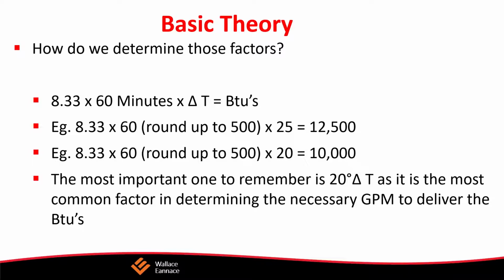Rarely will you use less than a 20-degree delta T. Occasionally you will use more. So if you're figuring a system out at 20-degree delta T, you're pretty much going to be safe that you're going to have sufficient flow to provide heat for the space.